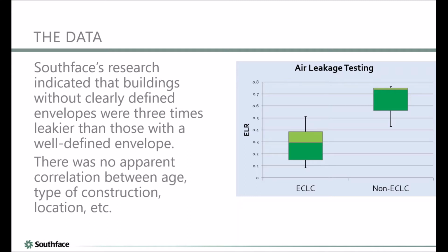If I remember too, we found that there wasn't really a correlation with the age of the building. We found new buildings that were unbelievably leaky. We found old buildings that were unbelievably leaky. We found new buildings that were tight, and we found old buildings that were tight.